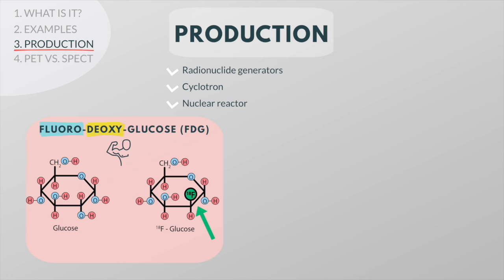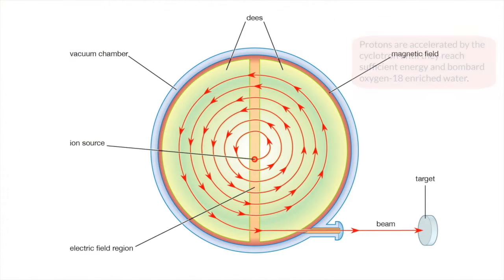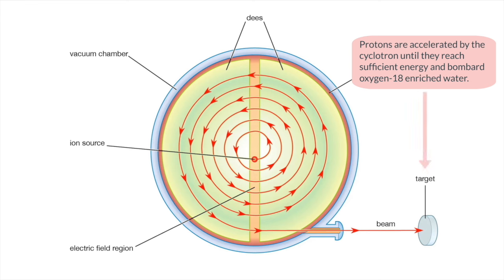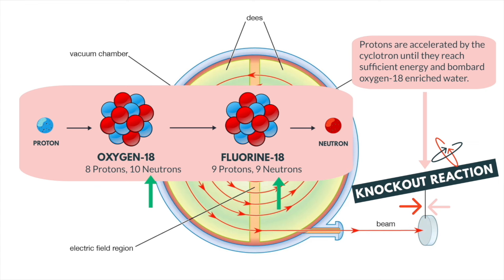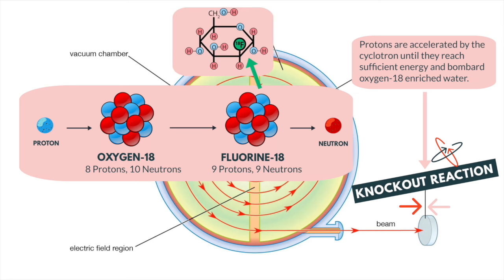Back to our first example about radioactive glucose. As with all radioactive fluorine-18 labeled tracers, the fluorine-18 must be produced on a cyclotron. Protons are accelerated by the cyclotron until they reach sufficient energy and bombard oxygen-18 enriched water. This collision causes a knockout reaction where an incoming proton knocks out a neutron in the oxygen-18, resulting in fluorine-18. The quickly decaying fluorine-18 is then collected and immediately attached to the deoxyglucose in a series of chemical reactions, resulting in the creation of FDG.